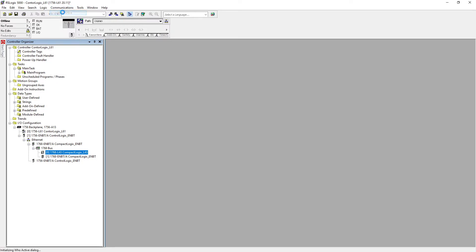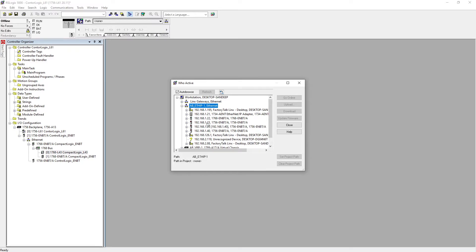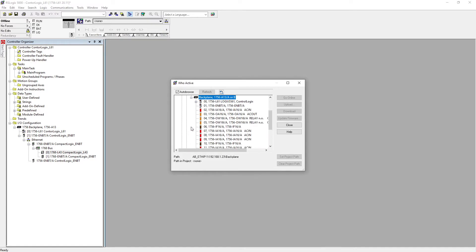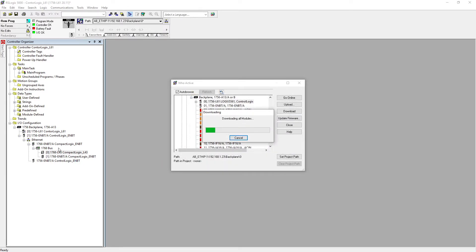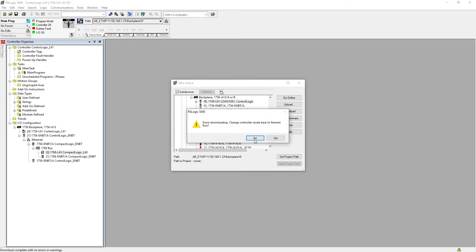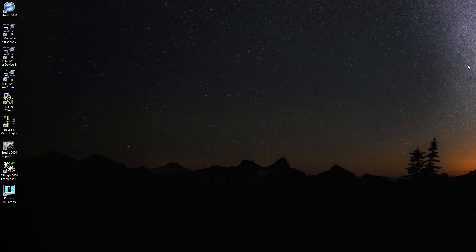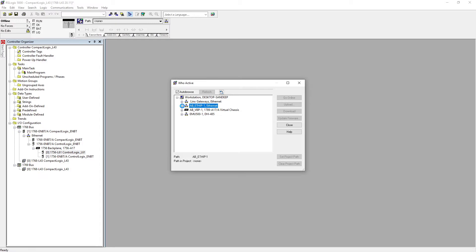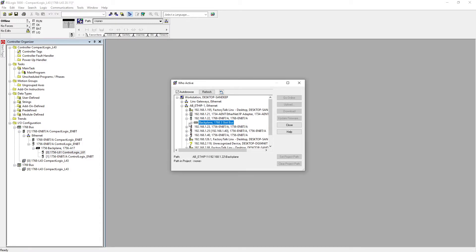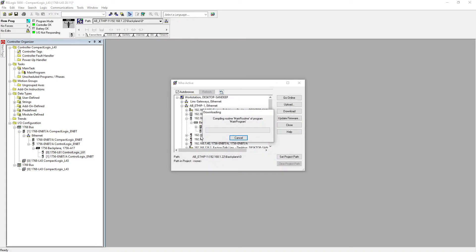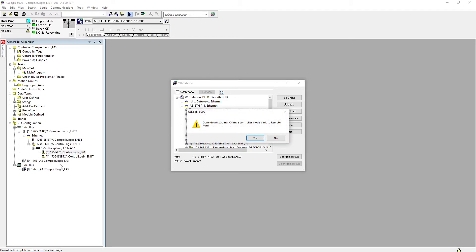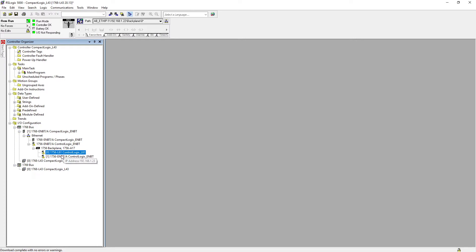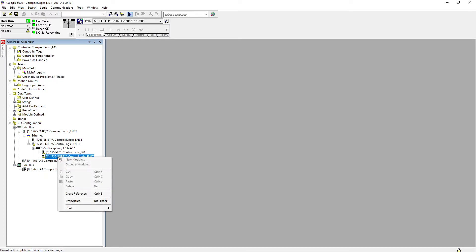So we're going to go 'Who's Active,' go in here — at .23, this is ControlLogix. Go to processor and download. We want to see that when we're downloading there shouldn't be any errors. No error — so everything is good on this side. Let's select now the CompactLogix side — 'Who Active,' go to Ethernet/IP, number .22 is my CompactLogix. Backplane — download. There are errors over here right now.